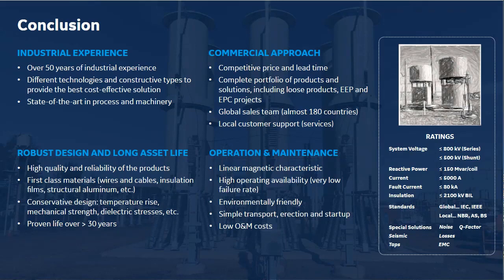The design of a reactor, although it's a very simple product, has several things that need to be checked, especially the insulation of the design. There are some questions about the transient. How do we design the reactors when there are very frequent and very high voltage transients? The design of the insulation depends on each case. We can get into deep discussions about that in a later section. But yes, there is a special design for high frequency, high voltage, transient issues. I would like to say insulation is one of the most important things when we're designing a reactor. So ask about it. We can discuss it.